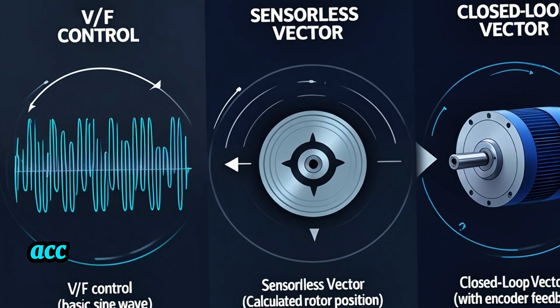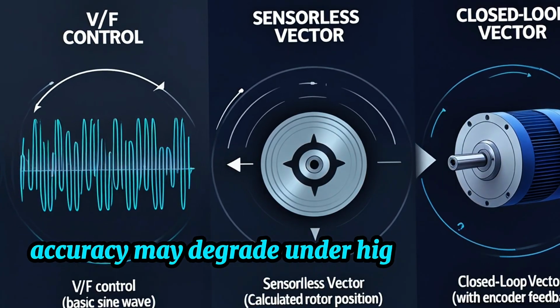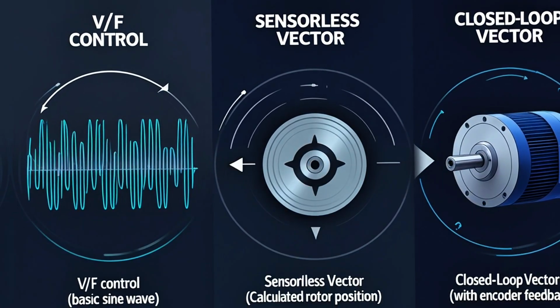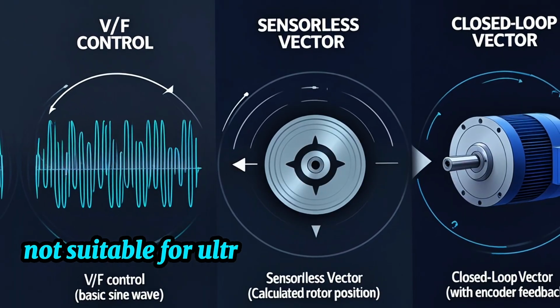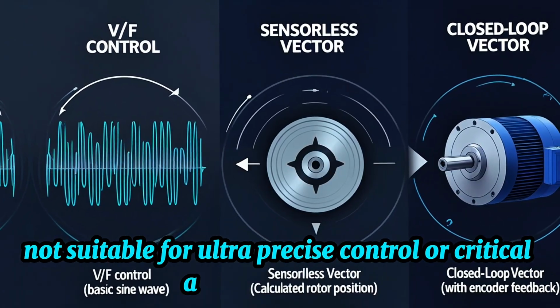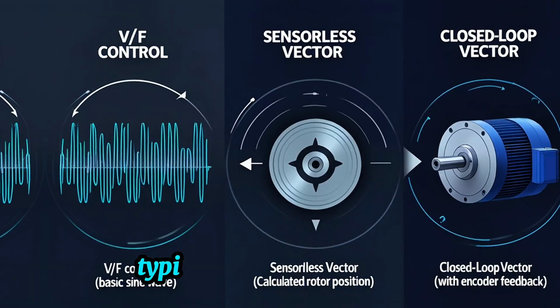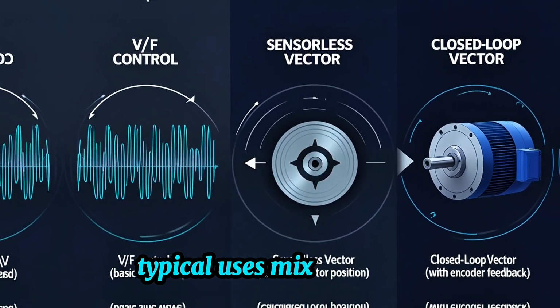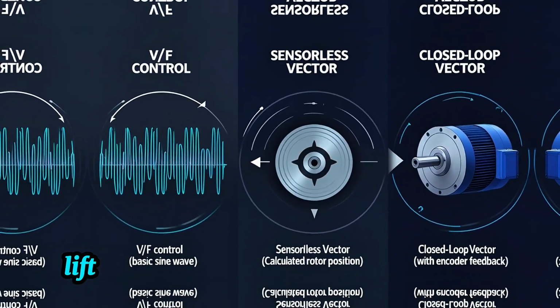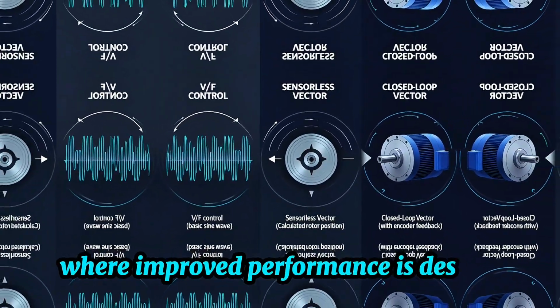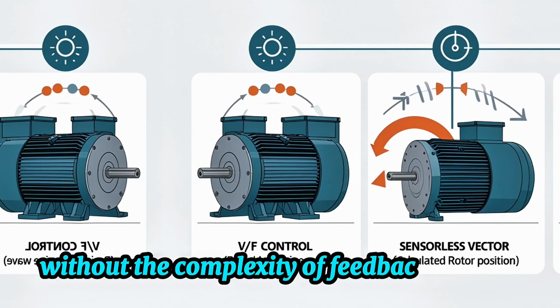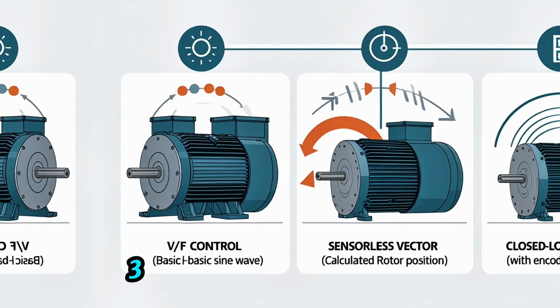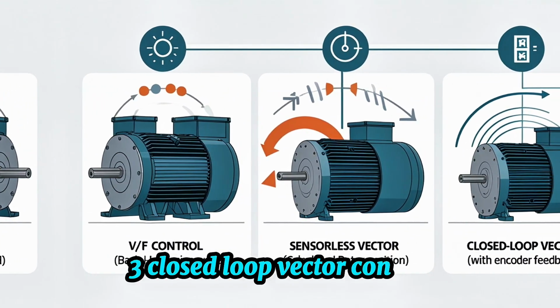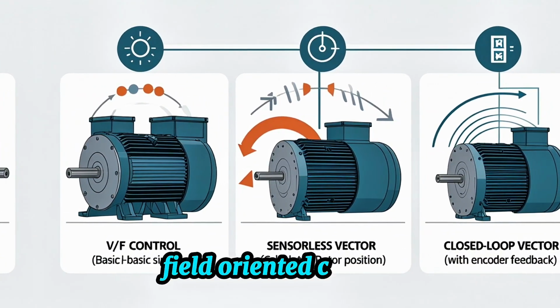Limitations: accuracy may degrade under highly variable load conditions. Still not suitable for ultra-precise control or critical automation tasks. Typical uses: mixers, crushers, lifts, and other variable load machinery where improved performance is desired without the complexity of feedback systems. 3. Closed-loop vector control, field-oriented control.